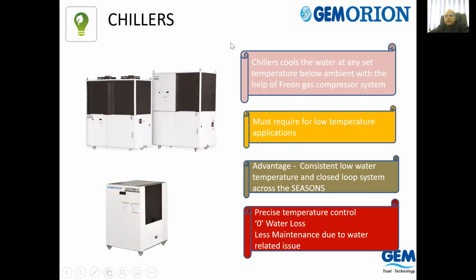Now the trend of using a chiller for cooling both low temperature, that is mold application, and high temperature like the feed throat as well as the hydraulic power pack cooling is becoming very popular. In fact, in Japan, for our principal supplying to Fuji, a single chiller will cater to both the molds as well as the high temperature oil application, with either a thermostat valve or temperature operated solenoid valves to maintain the specific oil temperature.